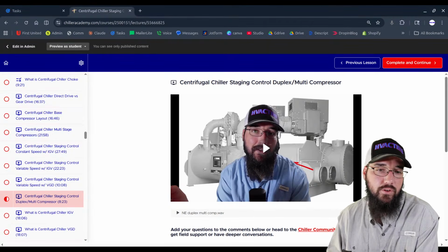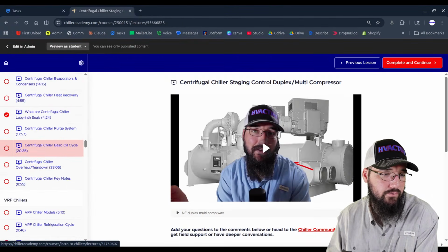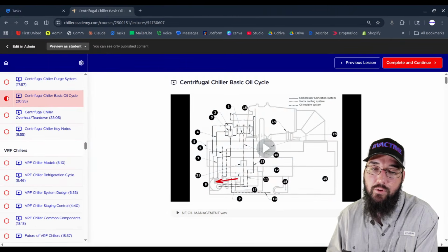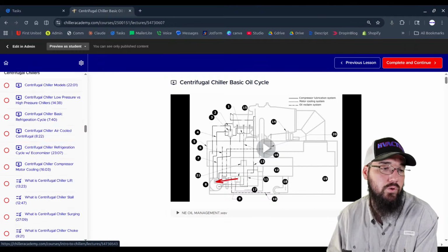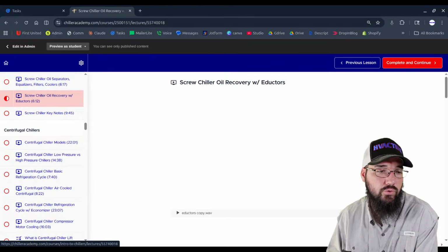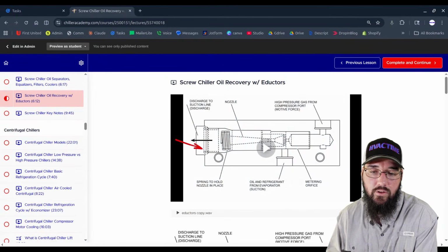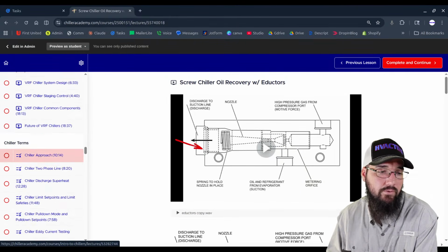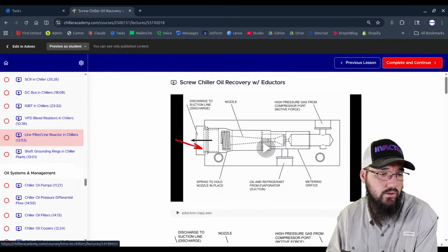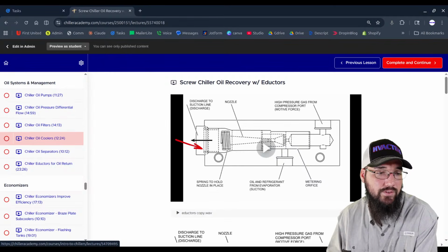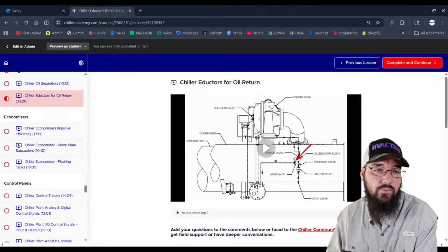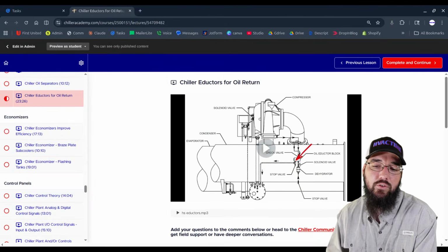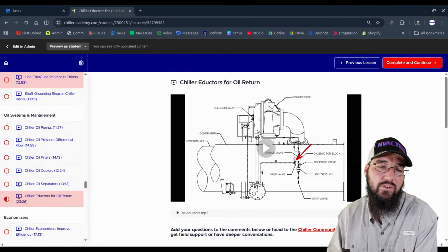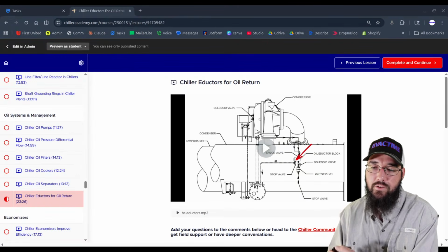And in terms of eductors, if you're in the course, centrifugals have their own oil cycle, where I explain this from a centrifugal standpoint as part of the oil cycle. I also explain this on the screw side. I've got a whole lesson dedicated to screws with eductors. You can review both of those, but then I have a module on oil systems and management, and in this I completely break down the eductors for oil return in general. I go much deeper here, hyper focusing on just the eductors and not the whole oil circuit as much. But this ties into the other two, so those three lessons all play into each other. And yes, exactly, it's a Venturi effect. That's exactly right.